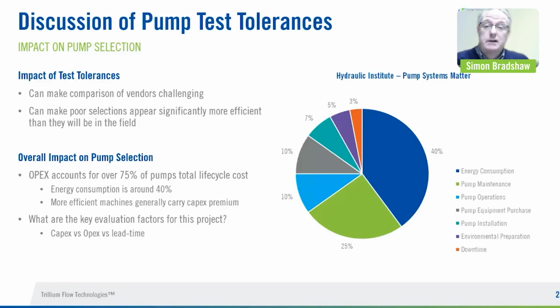The purchase of the machine is only around 10-12% of the total life cycle cost. The vast majority of it is energy consumption, pump maintenance, pump operations. So, when we look at that and you say, okay, if I'm concerned about how much I'm going to spend over the lifespan of this machine, it's really important that I look at how much I'm going to spend on energy consumption, how much I'm going to spend on maintenance, things like this, and that then drives the testing that I'm going to want to specify and the tolerances that I want to apply.